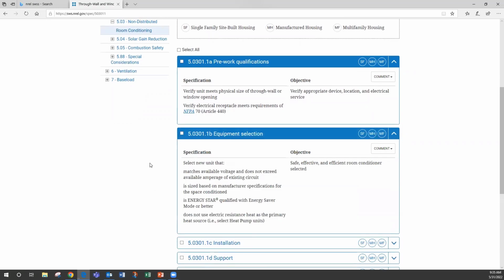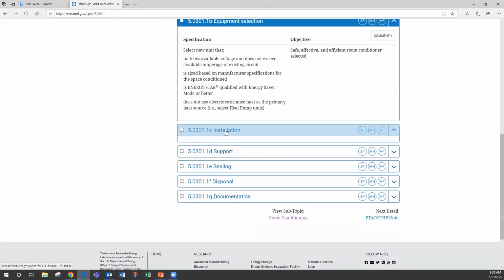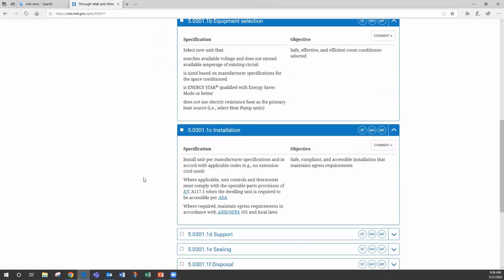Equipment selection matches available voltage, does not exceed the available amperage of the existing circuit, is sized based on manufacturer specifications for the space condition, is Energy Star qualified and energy saver mode or better, and does not use electric resistance as primary heat. If it was a unit that also supplies heating, they want you to select a heat pump. Basically, they don't want you to use resistance. Installation: install unit per the manufacturer specifications in accordance with applicable codes. So those installation instructions really become part of your inspection process.